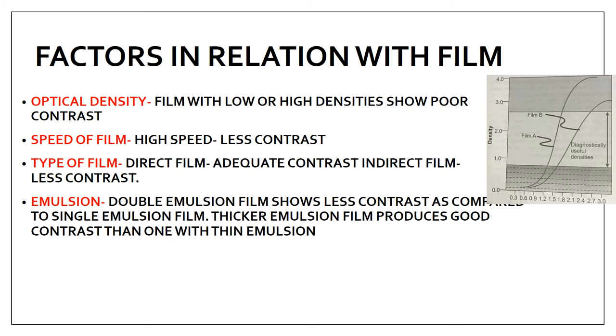The next are the factors in relation with the film. The first is optical density: films with high or low densities show poor contrast. The film should have a proper, optimally useful density so that you have proper contrast. Here is a characteristic curve — it shows the relationship between density, contrast, exposure rate, speed of the film, and latitude. As you increase the exposure rate, density goes on increasing. The density and contrast should be in the proper range to be useful for your film.